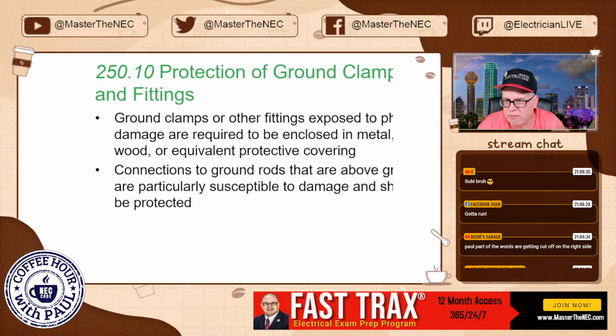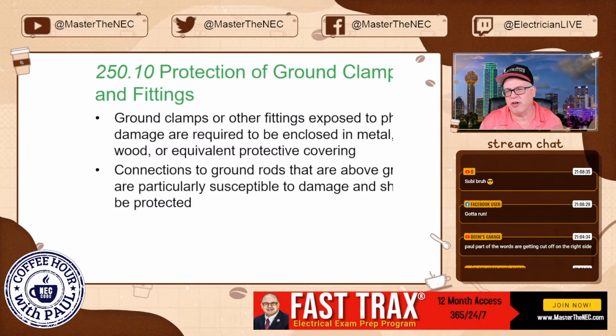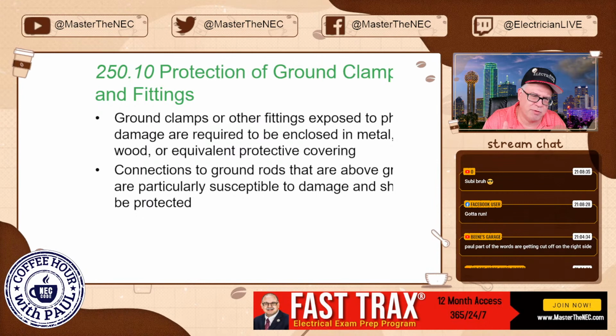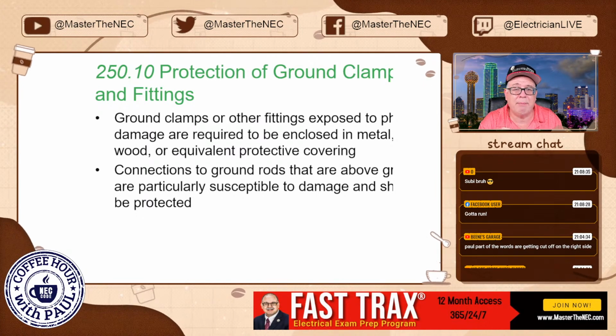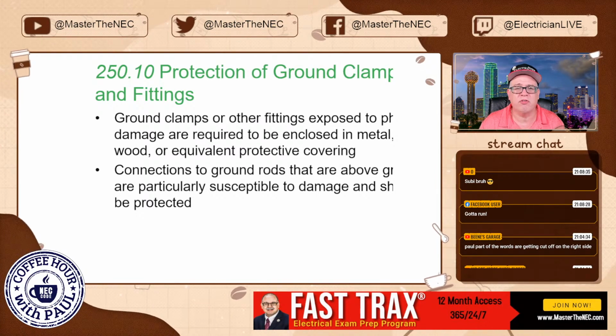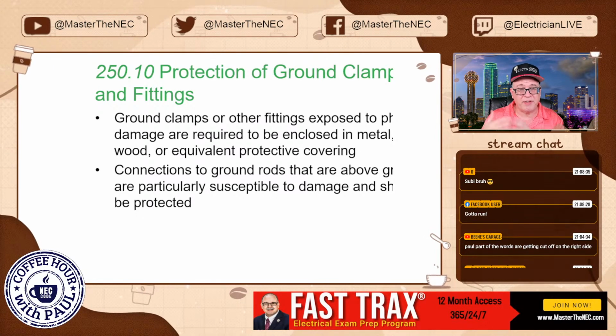Okay, well, we'll say it's a 10-foot ground rod, and they do have 8 foot in the ground, but they left a foot up for whatever reason. If that ground clamp is on it, then it is exposed to physical damage. You're supposed to protect it.